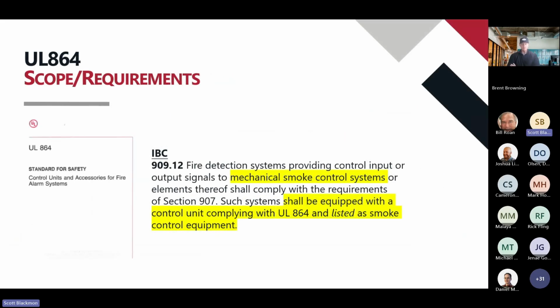So UL 864. UL 864 and IBC have kind of walked alongside one another. IBC up till about 2018 said, hey, you should look at UL 864, their design requirements, their design guide. It's a great way to model your stairwells. Well, after 2018, IBC said you shall comply with UL 864. So your equipment has to be listed to it, but it's not just your equipment, it's the programming and everything else that goes into it as well, the communication system.